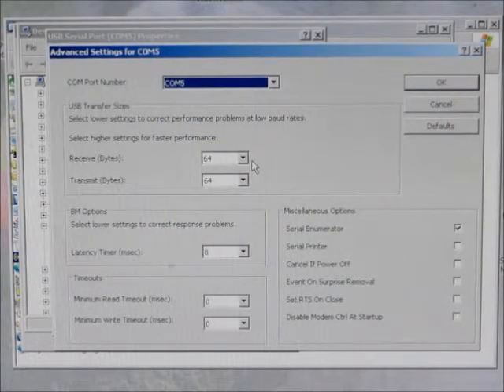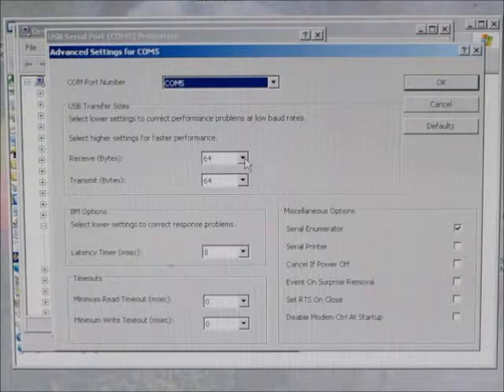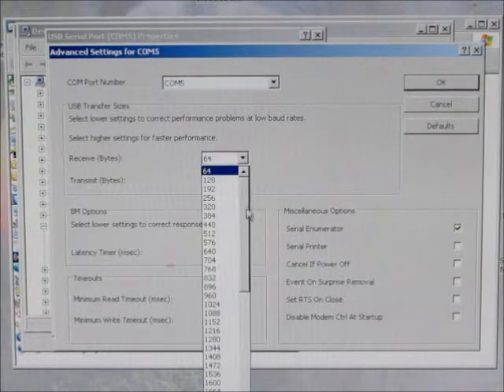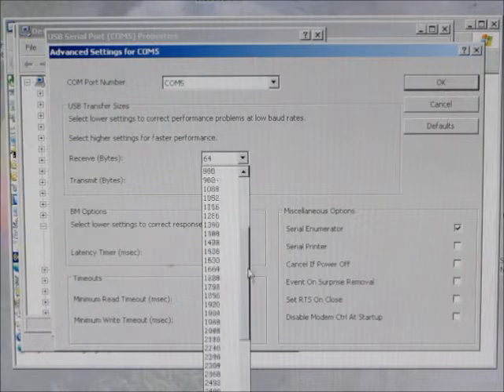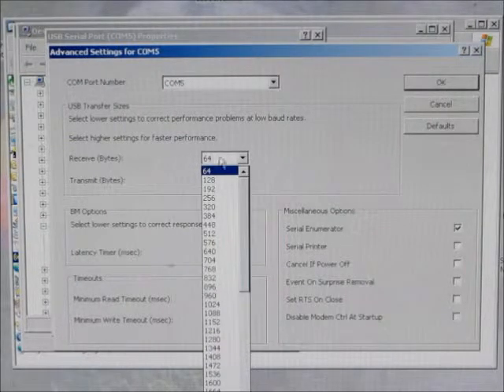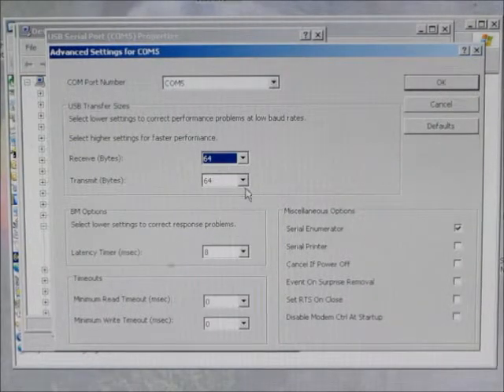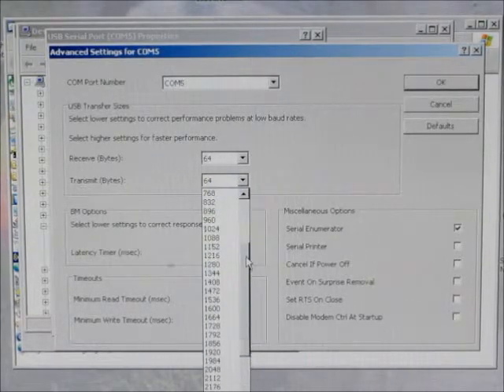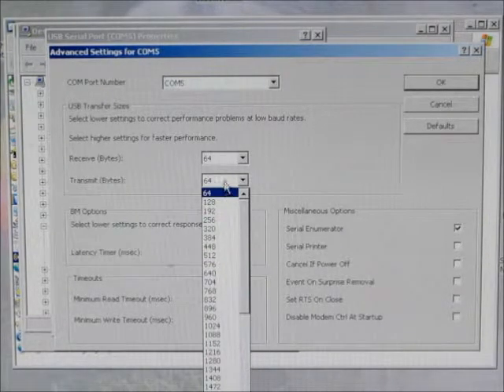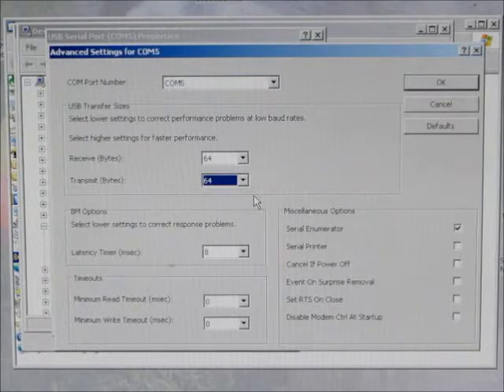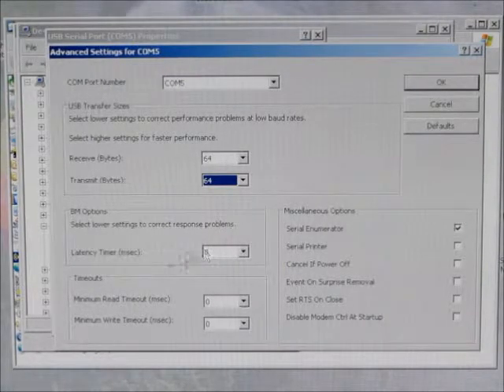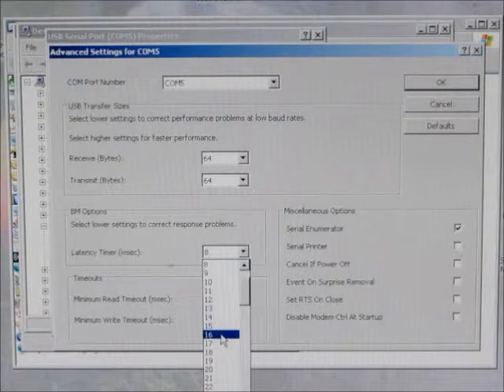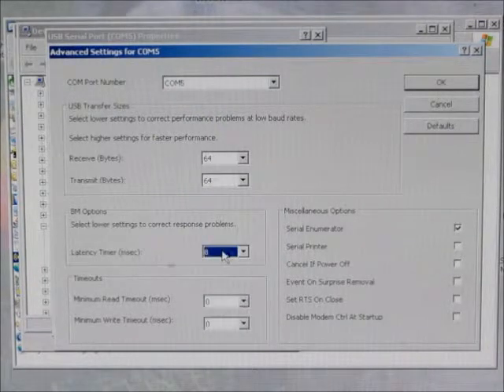The other parameters that you want to select: the receive buffer has a default value of 4000 or something like that. You want to lower the receive buffer value to 64. The transmit buffer also will default to 4000. You want to set that also to 64. And lastly, there's this latency timer that the default is 16. Go ahead and set that to 8.